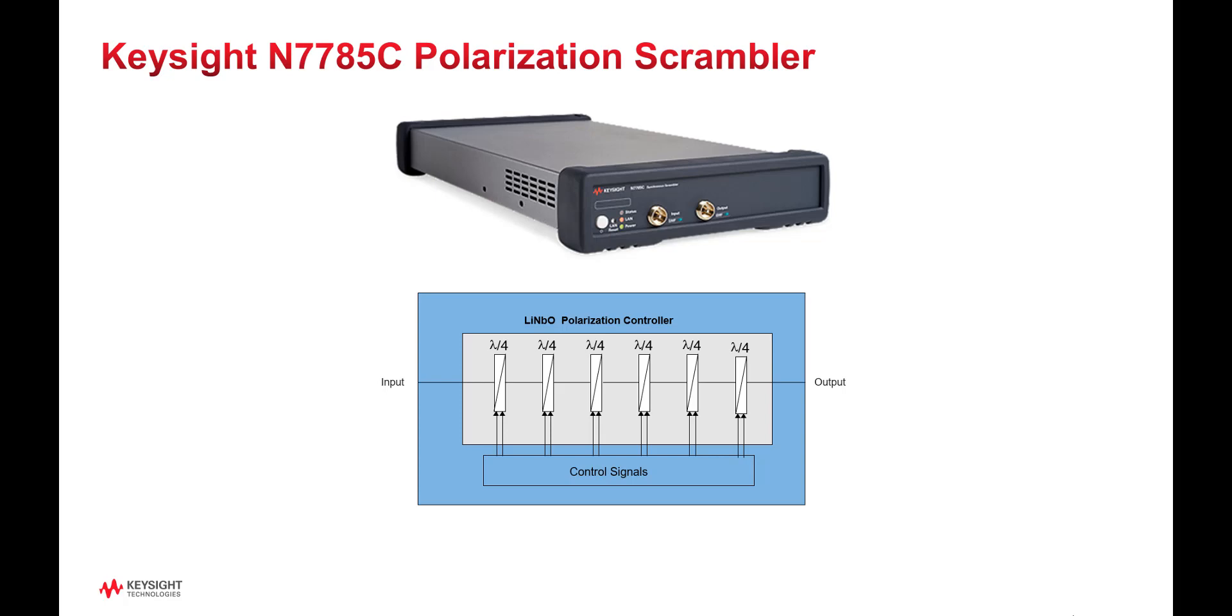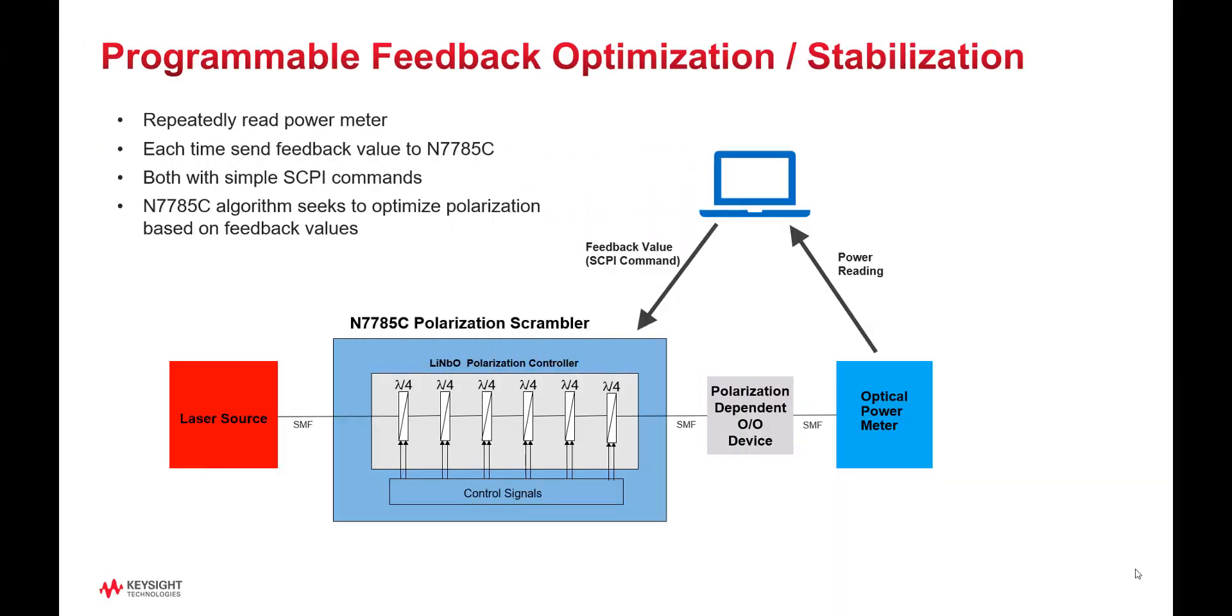It is programmed with SCPI commands with its LAN or USB interfaces. The instrument's firmware contains an algorithm that will optimize the polarization iteratively based on feedback values sent to it with a simple SCPI command.